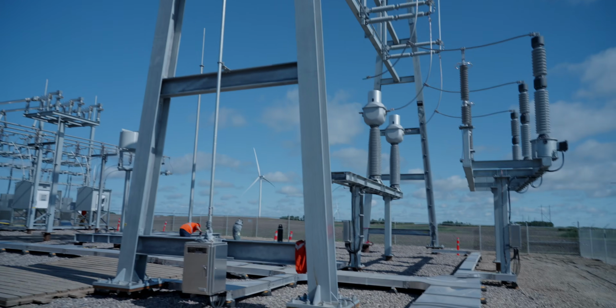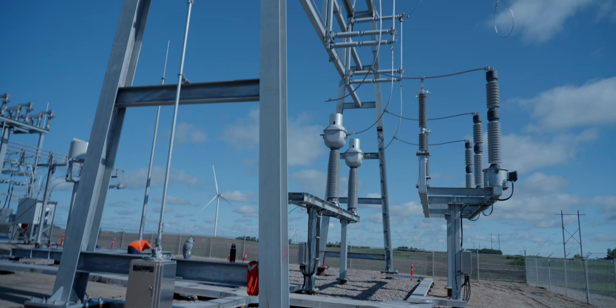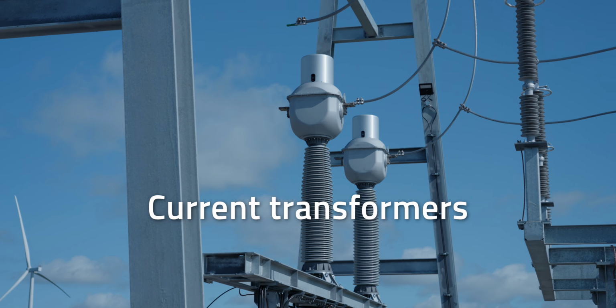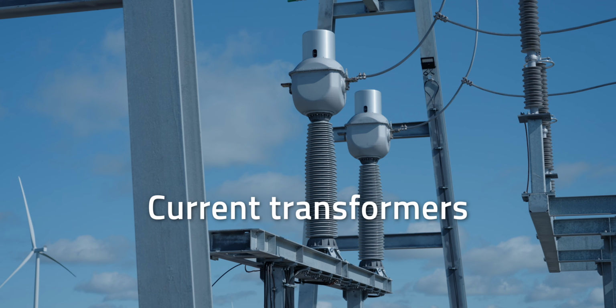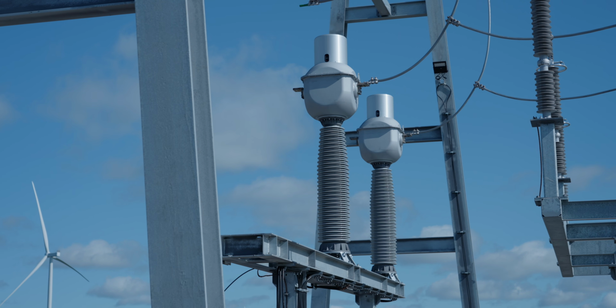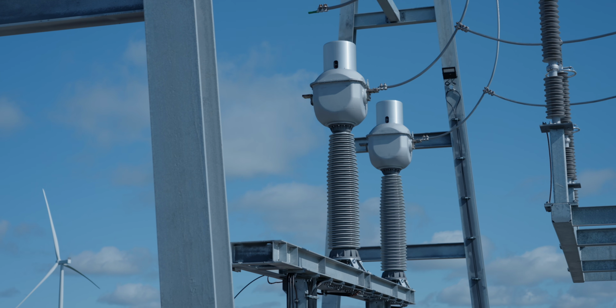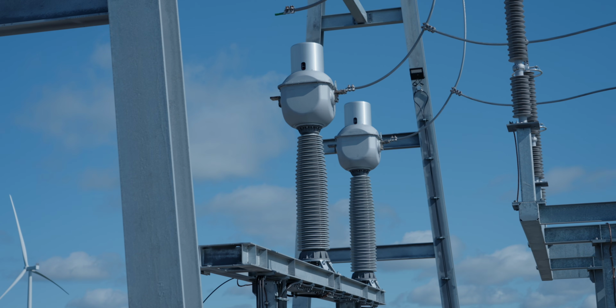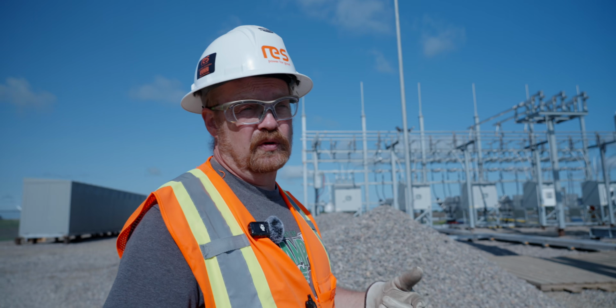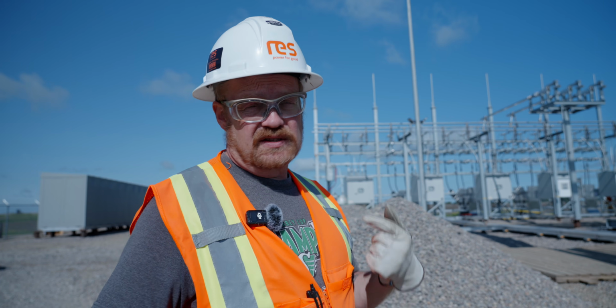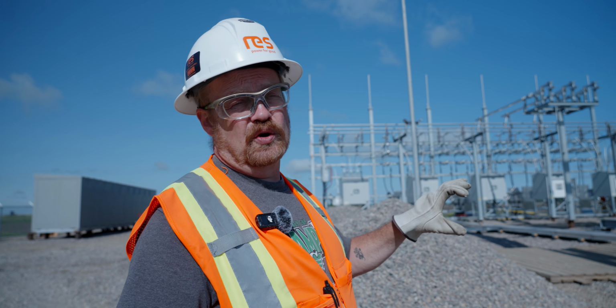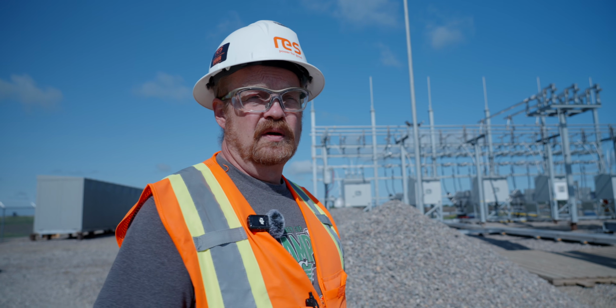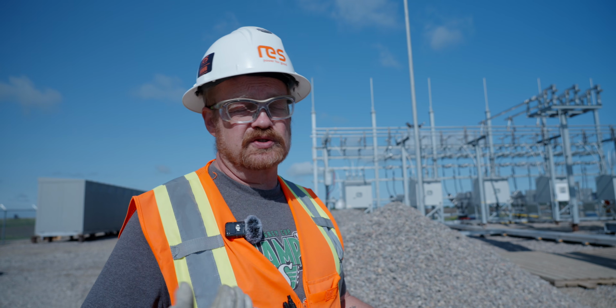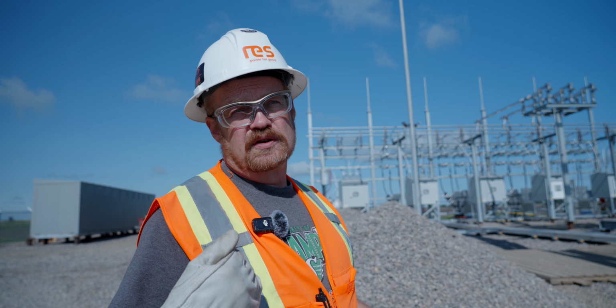What are those devices on the left? Those are current transformers. What those do is take the amperage flowing through the line and reduce it by a known ratio, then through secondary wiring it goes inside the building for both metering and protection. There might be up to 500 to 600 amps flowing through the line, and you don't want that in the building for safety reasons. So they drop it down by a known ratio to a safer value for use in the building, and any equipment in the building knows that ratio so it can mathematically step it back up, giving you an assumed value.